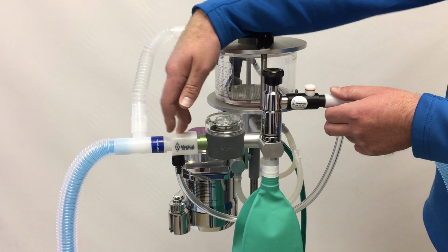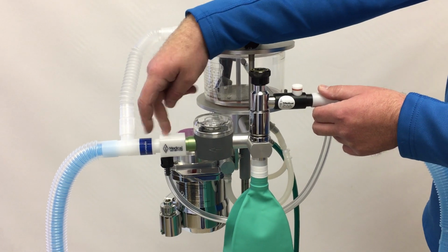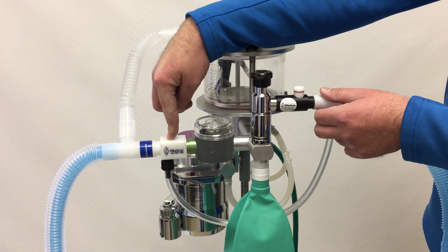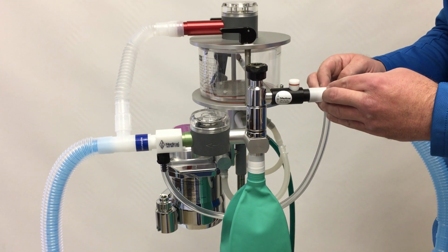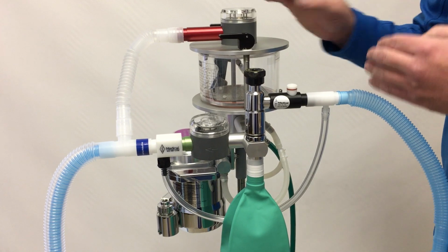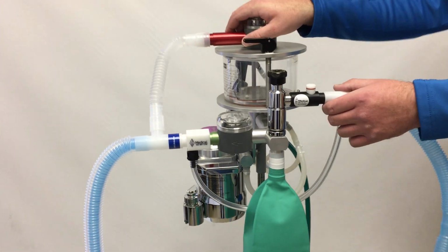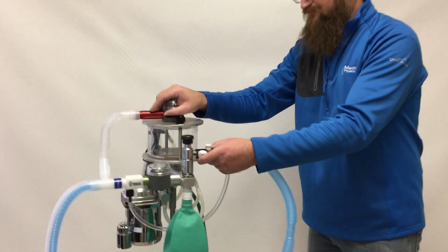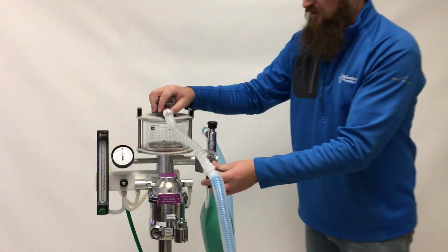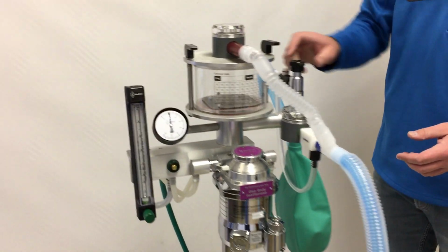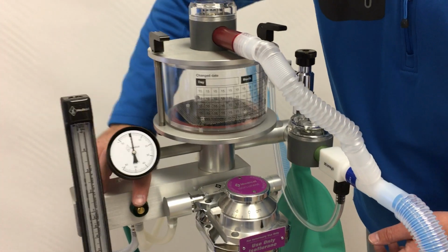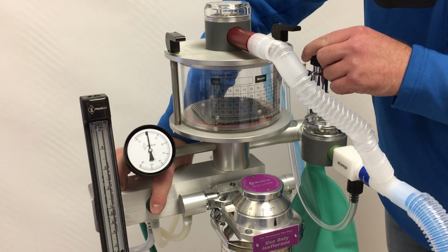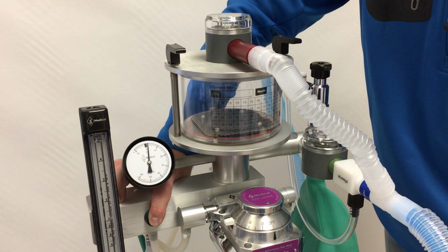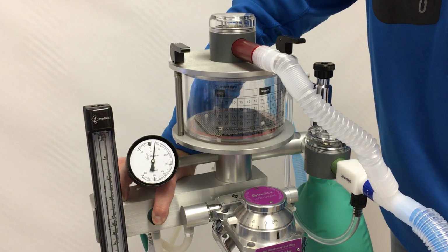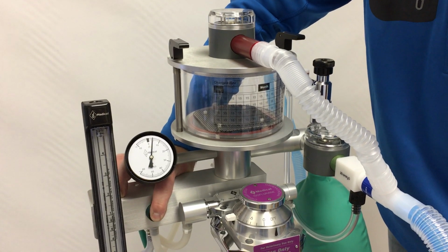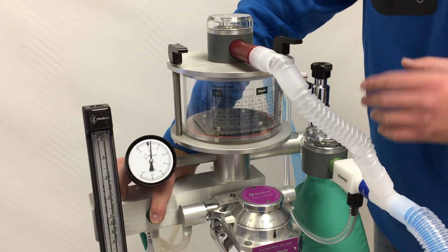They're sized appropriately, 22 millimeter for fresh gas connections on the safety valve and 19 millimeter for exhaust, so they really should not be interchangeable without some serious effort. So we'll turn this back around, and now with the safety pop-off valve in there, if we build up pressure with the pop-off valve open, if we add gas in, it's not going to open because we aren't able to build up enough pressure. It's not functioning, it's not exhausting.